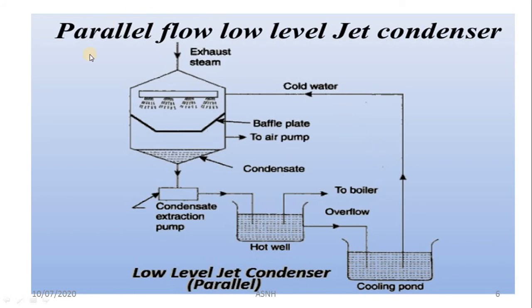It enters from the top side of the vessel, or the top side of the shell, and simultaneously mixing of these two different fluids takes place. Because of that, heat transfer occurs and latent heat of condensation takes place, and due to that the phase change occurs from vapor to liquid, that is water. That water is known as condensate, and that condensate is collected and stored in the hot well through the condensate extraction pump. The main function of that condensate extraction pump is to allow condensate from the bottom of the shell to enter into the hot well.